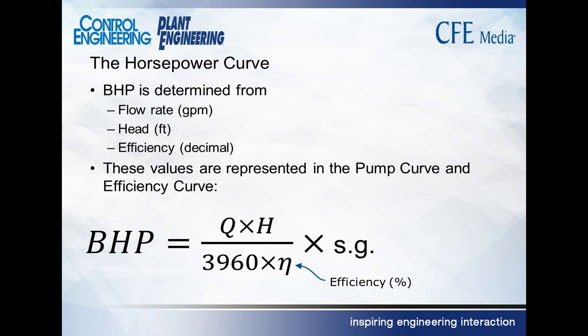Q in this formula is for quantity or volume or flow. H is for head. BHP is the brake horsepower. The little Greek character down here, eta, stands for efficiency. So really simple formula. Incidentally, the SG on the end is for specific gravity, but the specific gravity for water, and let's just assume we're pumping water because it makes it easy, is 1, and if you multiply by 1, we don't have to worry about it. So we have this very simple formula: flow times head, divided by a constant, in this case 3960, and then divided by efficiency equals horsepower.